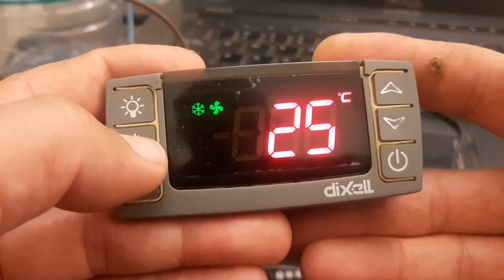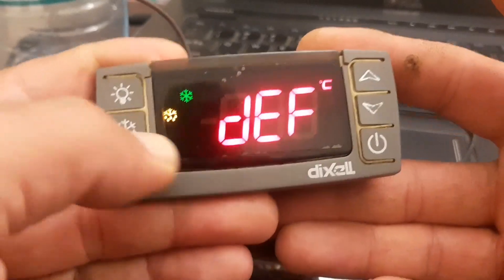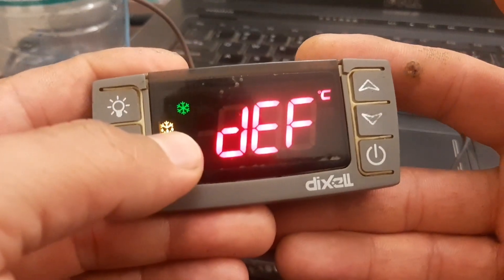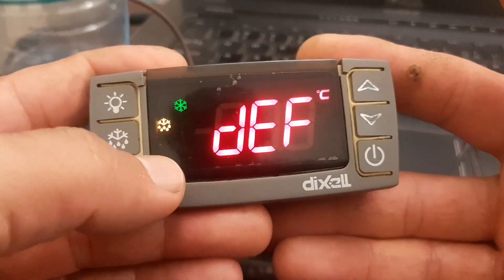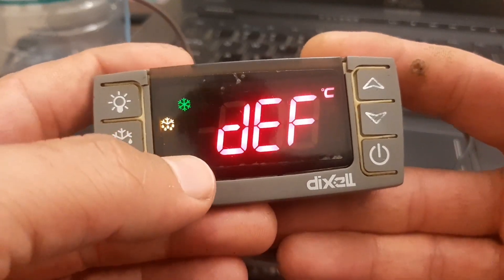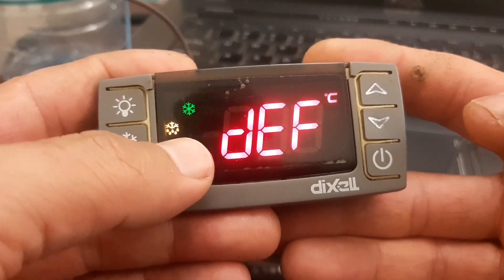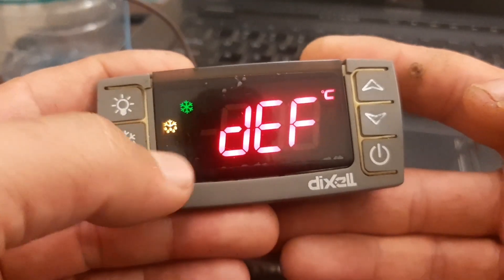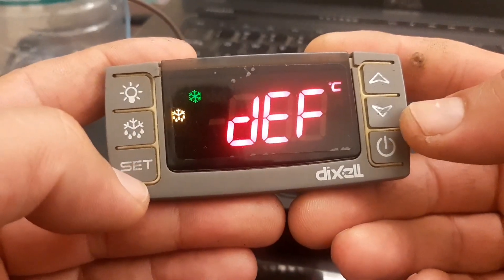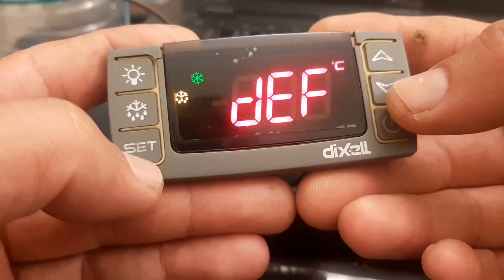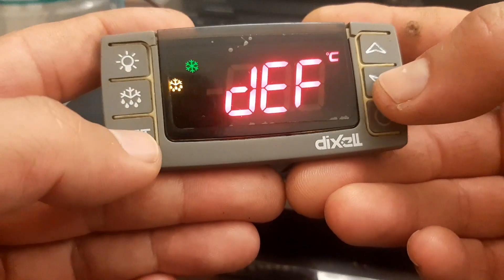When you long press the defrost key, you can see the defrost symbol turns on and also the compressor symbol turns on. This is because we selected hot gas - in hot gas mode, the compressor runs during defrost. If you change it to electrical heater, you will see the compressor symbol will disappear.